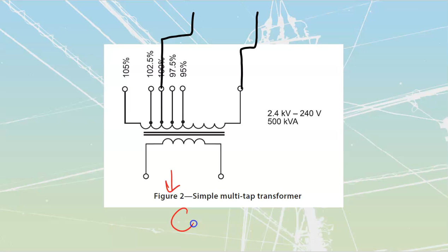What we'll do is we'll measure with our voltmeter. So I'm getting customers telling me things like, hey, I've got machines that are randomly starting and stopping. Sometimes my computer is glitching out. A lot of these are signs that the voltage is drooping too low, and low voltage protection is kicking in on a lot of industrial equipment. So I see my voltage is too low over here. I can take a reading off of this side over here.